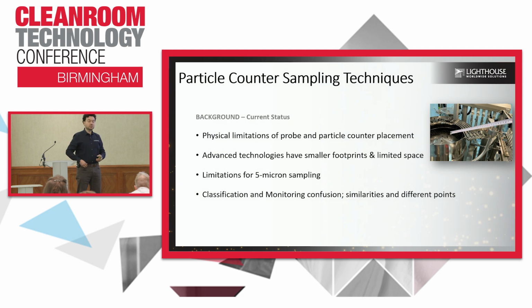Also, we all know that there are physical limitations because of the systems that are being developed by the companies, particle counter companies, and also limitations with the area that we implemented. For example, if you are working with isolators, you have a very limited space to place your sample tube, and also the device itself as a combination of these two. It's not always easy to have your particle counter right under the service area so that you will have one single line to sample all this out.